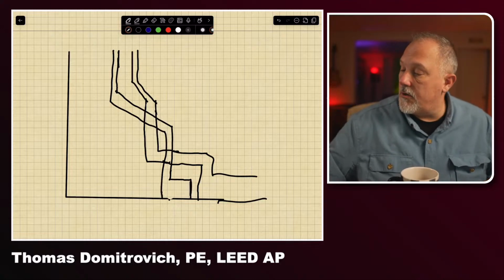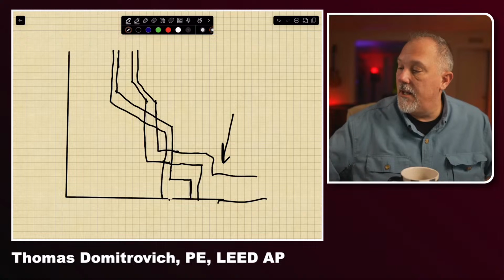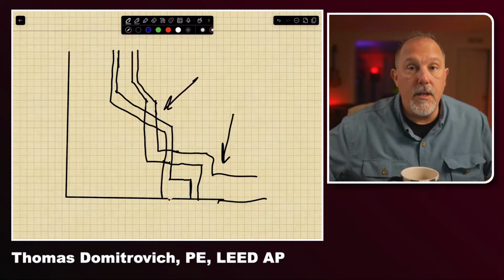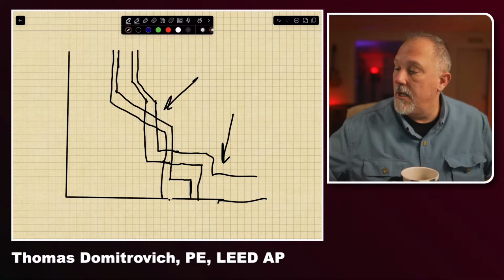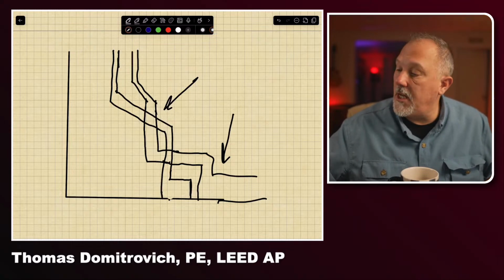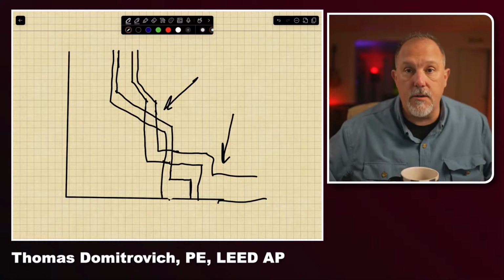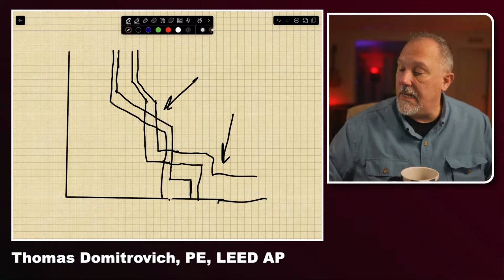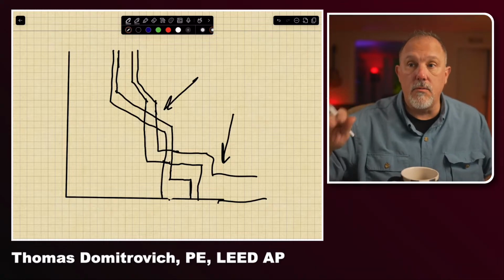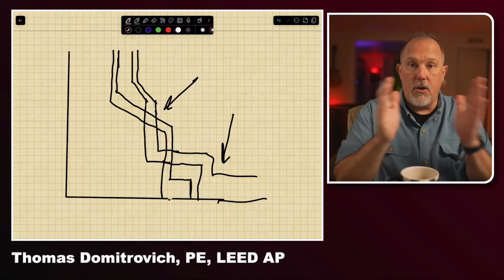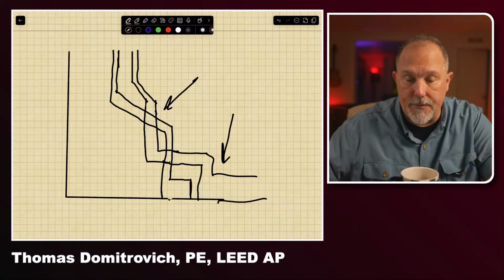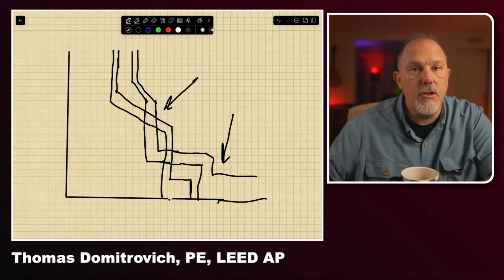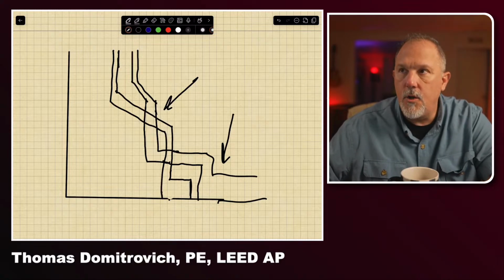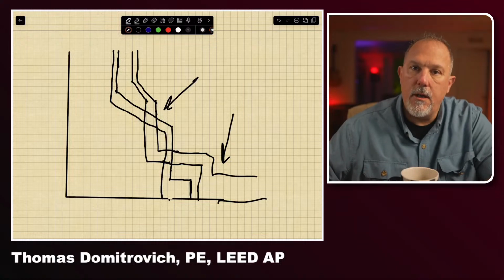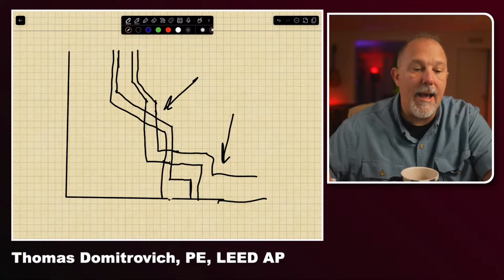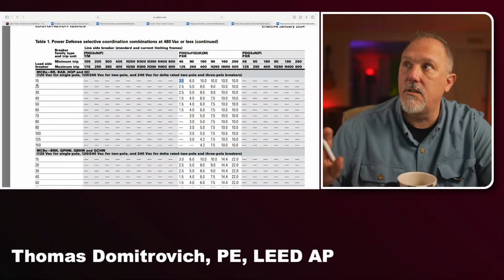So I can show a breaker like this. Those tables are going to tell you what happens in the instantaneous region. They're not going to tell you the overload region, your short time delay regions. So you need to make sure you plot those circuit breakers, especially when there is adjustability in the long time region. Those tables don't guarantee selective coordination in the overload regions. You still have to plot the curve and manage your set points. What the tables address is the three-phase bolted fault current value and what happens in the instantaneous region only.